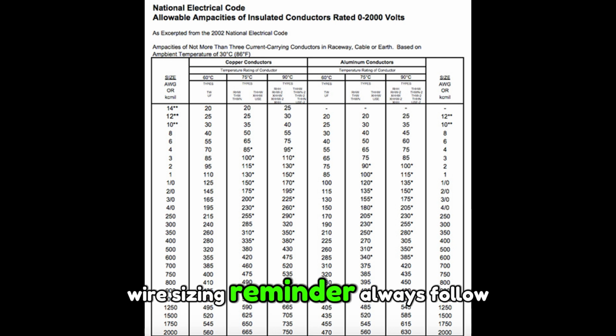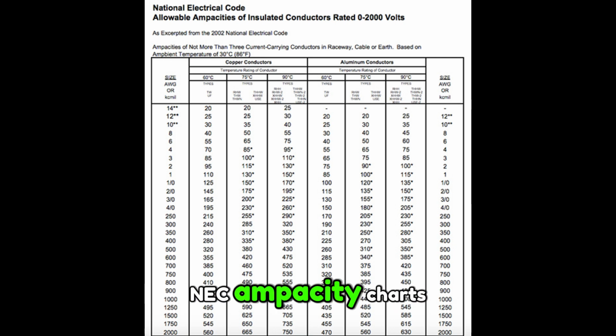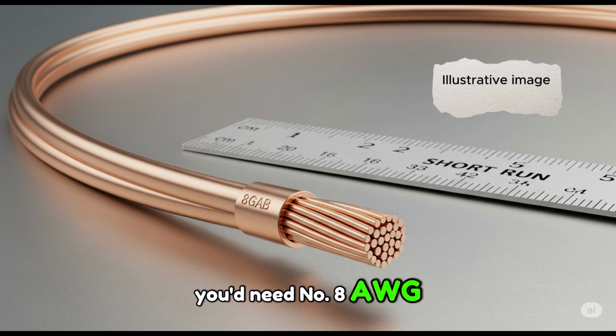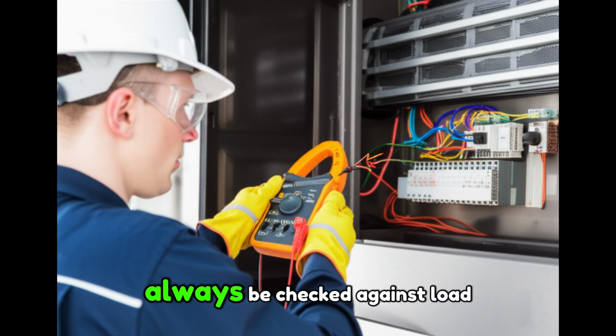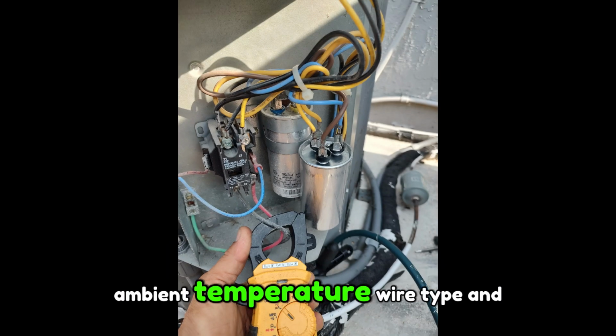Wire sizing reminder. Always follow NEC ampacity charts. If your load is around 32 amps, you'd need number 8 AWG copper wire rated for 40 amps. Breaker and wire sizing must always be checked against load, ambient temperature, wire type, and insulation.